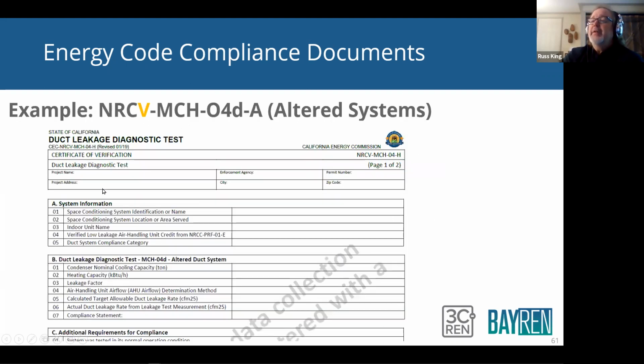Okay. Here's what it looks like, duct leakage. Okay, got the system name. There's one of these for each system, all right? System name, location, indoor unit name, condenser, nominal tonnage, leakage factor, calculated, targeted, allowed leakage, actual leakage, stuff like that, okay?